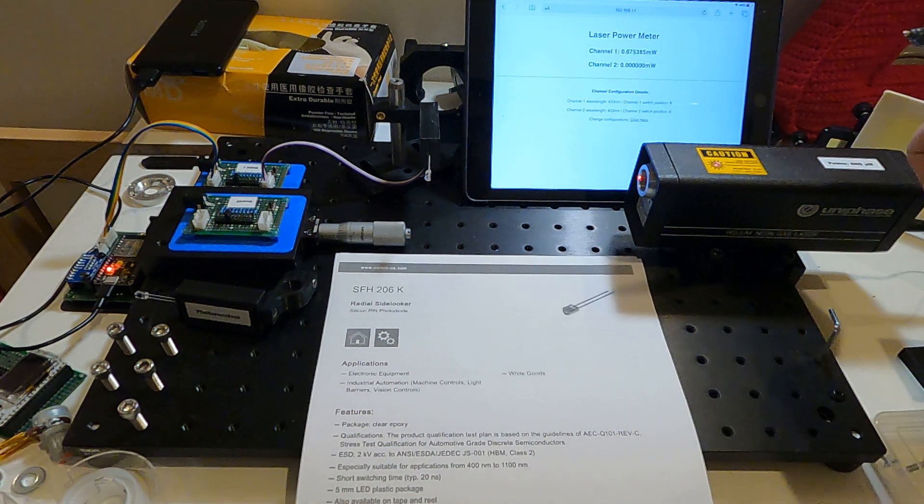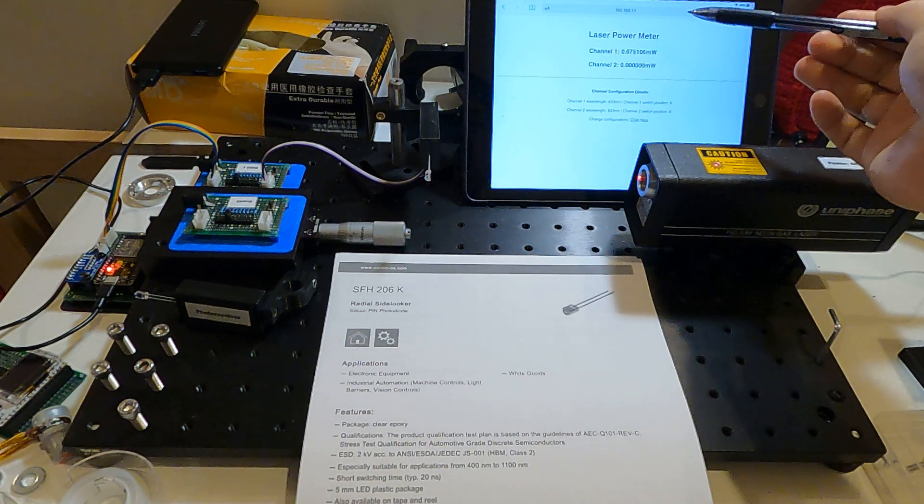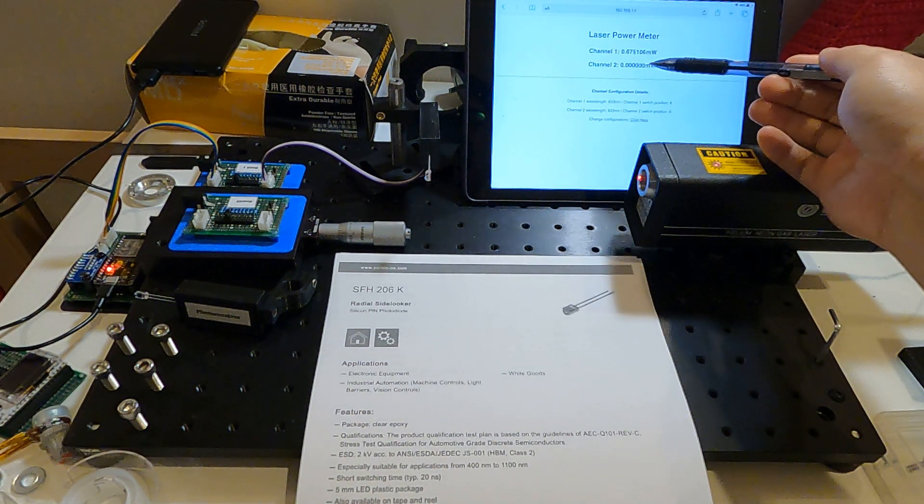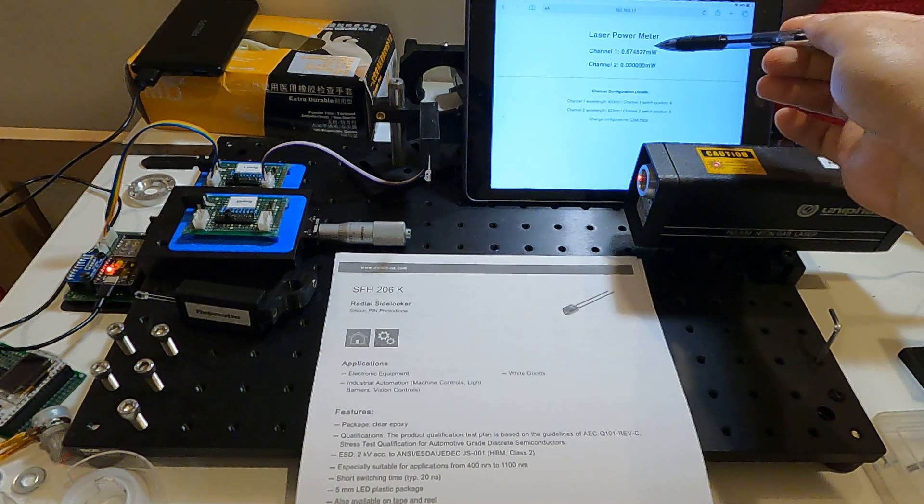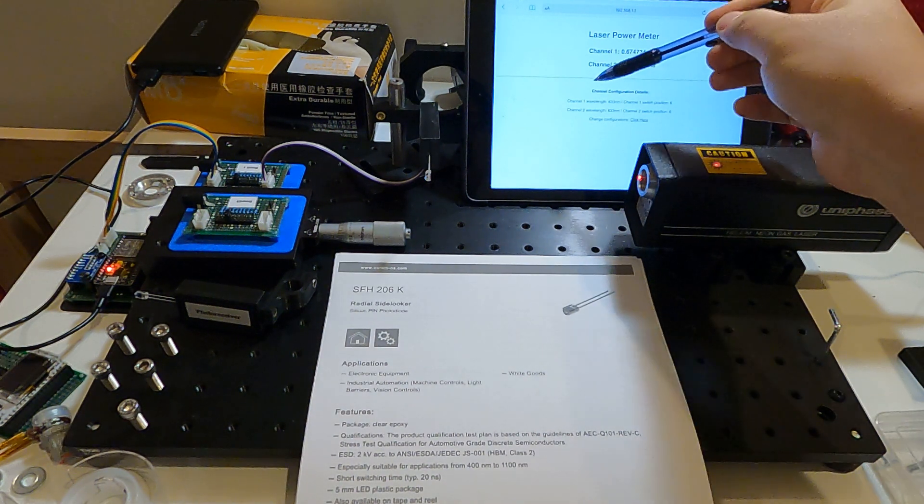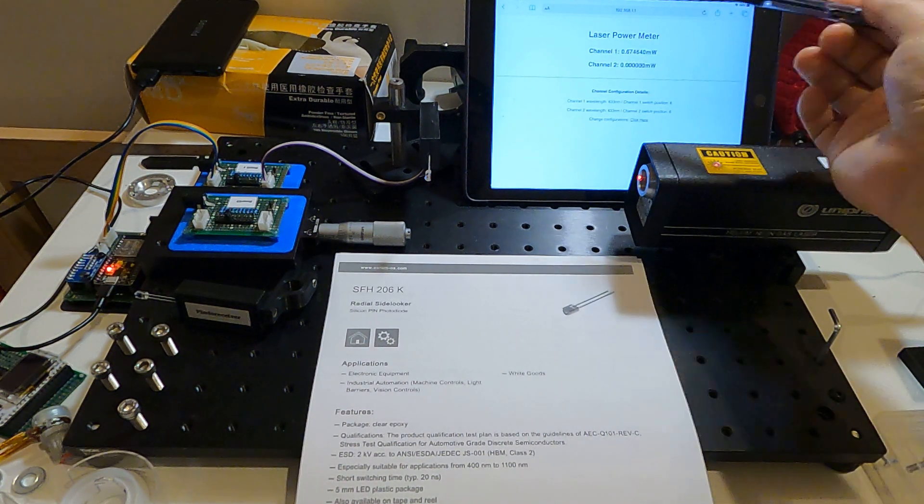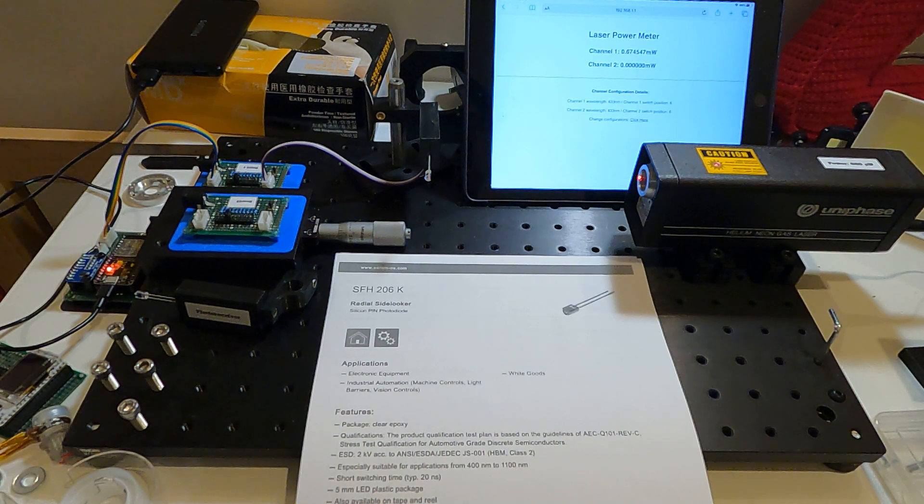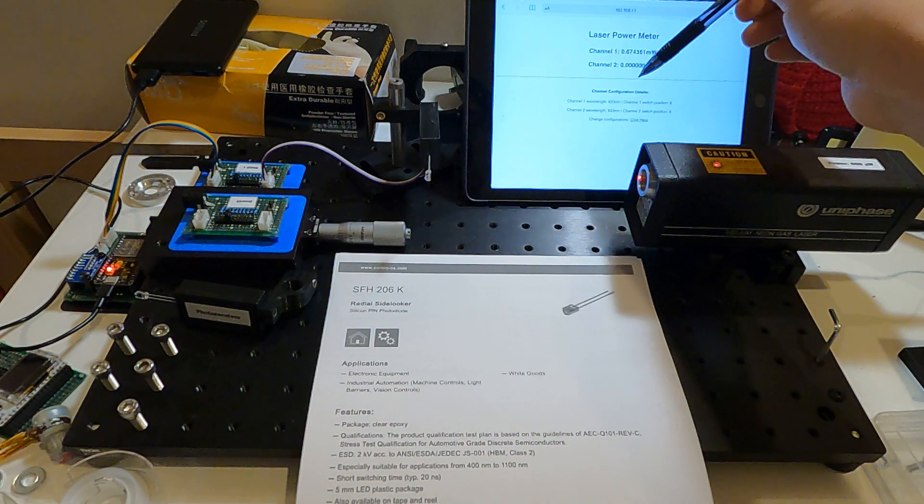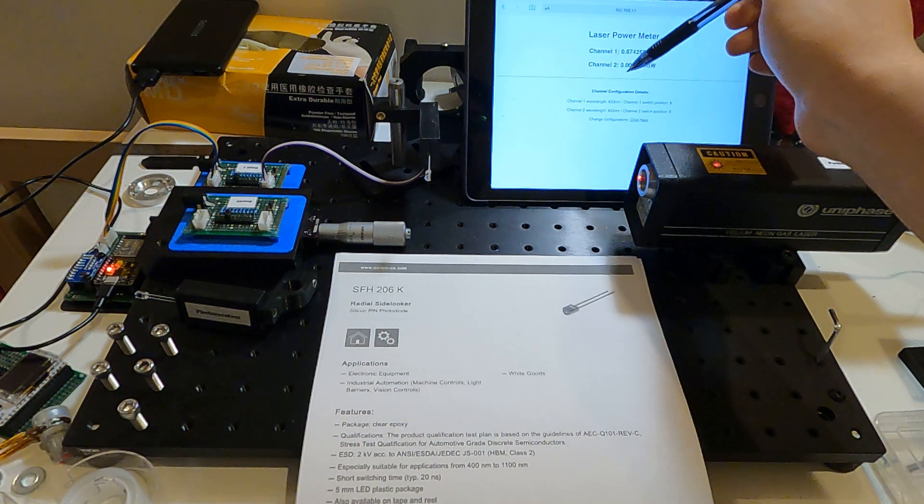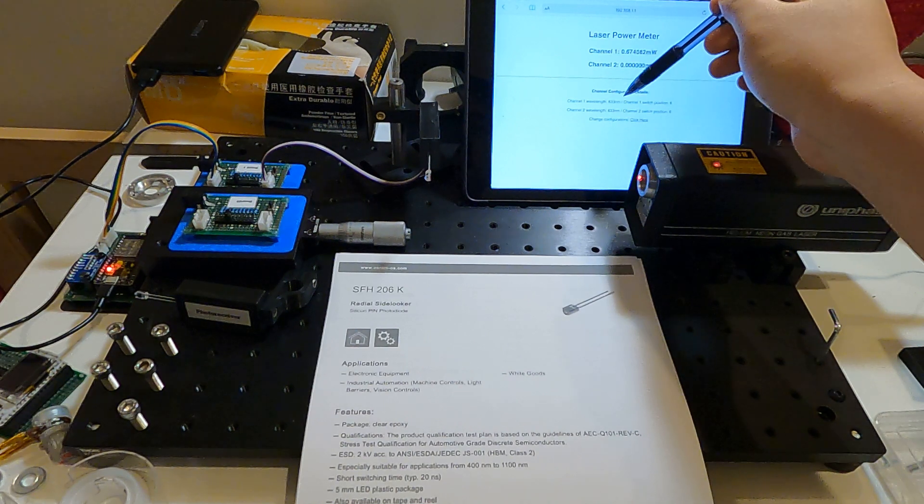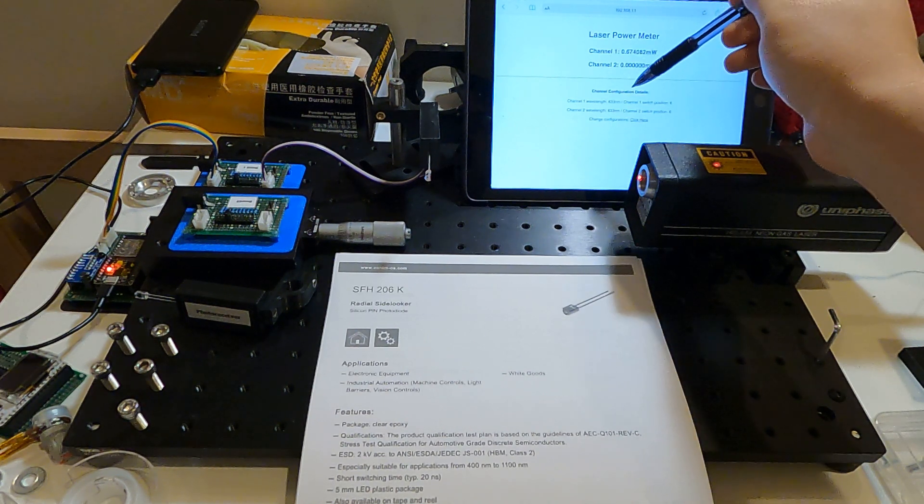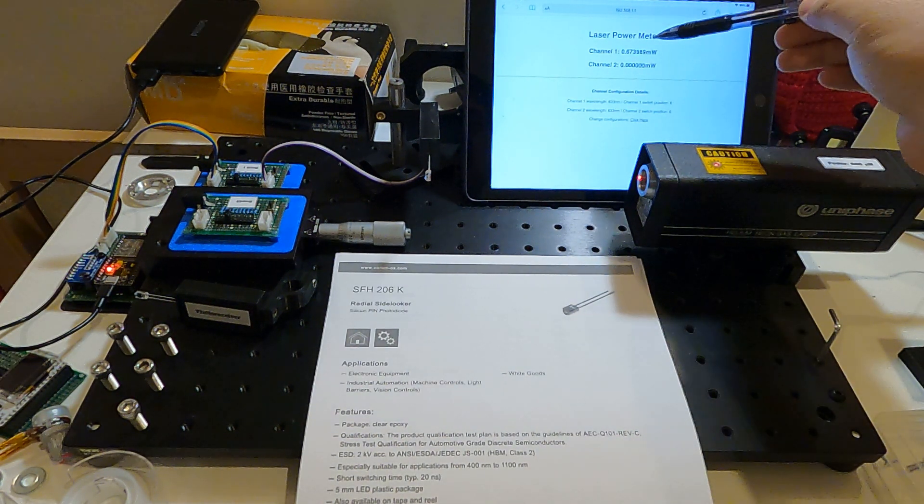I shut off the second channel so you can see the results from the first channel. Below is the channel configuration details. I set the channel 1 wavelength to 633 nanometers because currently this laser power meter measures the power from this helium-neon laser here.